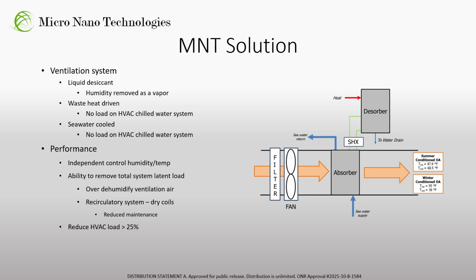The system is designed to enable the deep dehumidification of the ventilation air, such that when combined with the return air in the recirculatory system, the latent load within the recirculatory cooling system can be eliminated. This provides the ability to potentially operate the recirculation system cooling coils as dry coils, further decreasing the HVAC system load and improving system reliability. Based on the program's Phase 1 analysis, this system has the potential to reduce the shipboard HVAC load by greater than 25%.